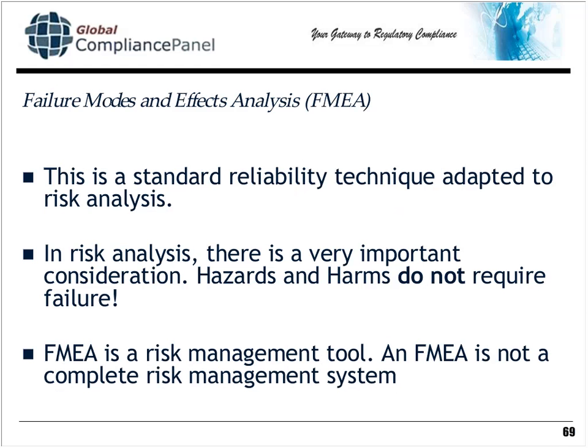Now, FMEAs come from reliability, and there the issue is the fault, right? What you're trying to do is understand how often things fail and the consequences of these failures. So FMEA is a good risk management tool, but it's not going to be a complete risk management system. It's going to help you identify failures, and those failures can then turn into hazards. Right, but that doesn't mean that all hazards are failures. There are hazards that are not failures and not going to show up in the FMEA.